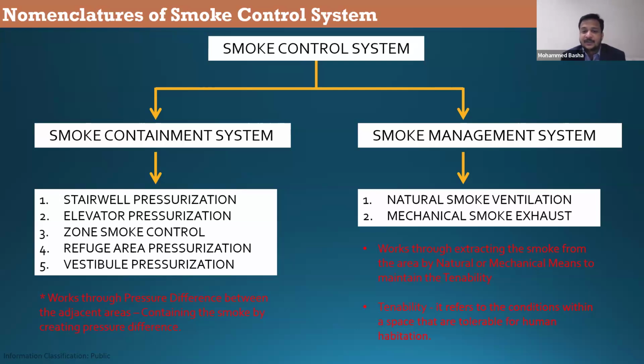The next item is the smoke management system, which has a completely different working concept from the smoke containment system: natural smoke ventilation or mechanical smoke exhaust system. This works by extracting the smoke from the area by natural or mechanical means to maintain tenability. What is tenability? Tenability refers to the condition that is suitable for the occupants to evacuate, or for the occupants to be in that space. That is called a tenable condition. So the main purpose of the smoke management system is to create a tenable condition for the occupants to leave the area affected by fire. Whereas the smoke containment system prevents the smoke from entering one area from another by pressurizing the non-affected zones, the smoke management system extracts the smoke, and the smoke will still be in that enclosure, but at a higher level.